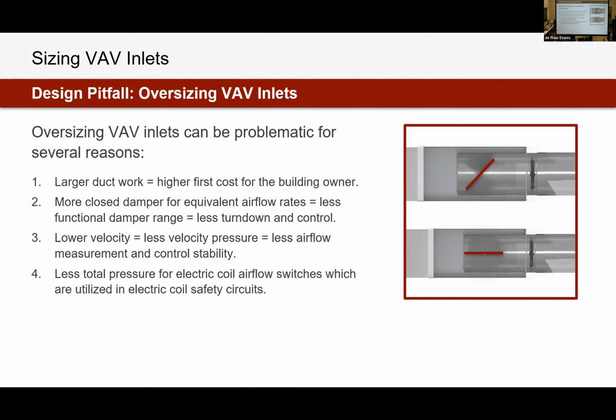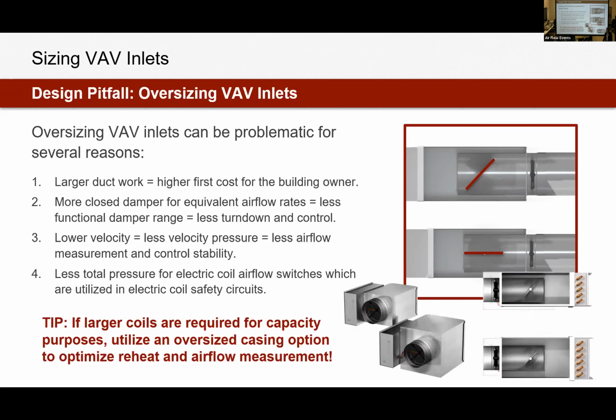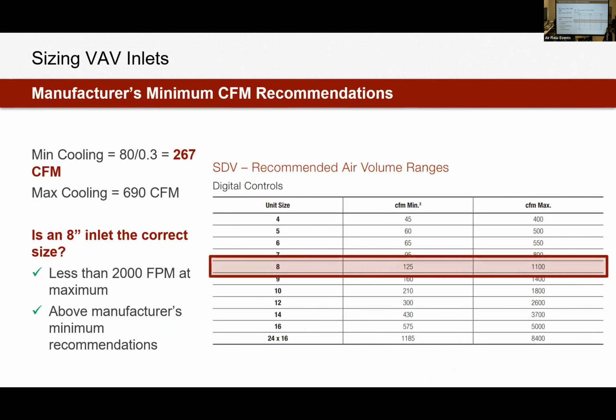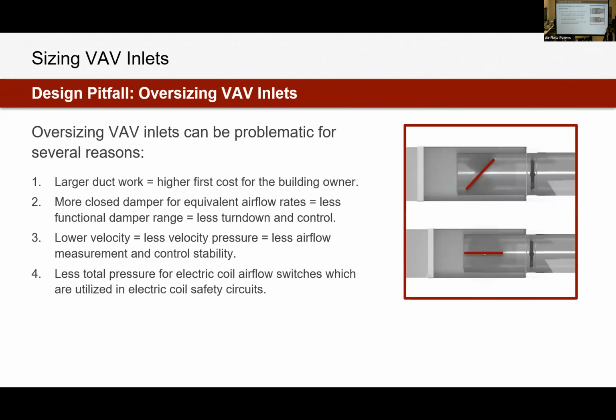We also have lower velocities when you're pinching off that valve. You've got lower velocity pressure, and again, it's a little bit harder to measure. And then finally, if we have an electric coil on this box, with those lower velocities, it's going to be a little bit harder for our pressure switch to close to run the electric coil. So oversizing could be okay, but you could run into a scenario, go back here, where we jump to the next box size and maybe we end up out of that range. So something to be mindful of if your company standard is just to automatically upsize inlet valves.